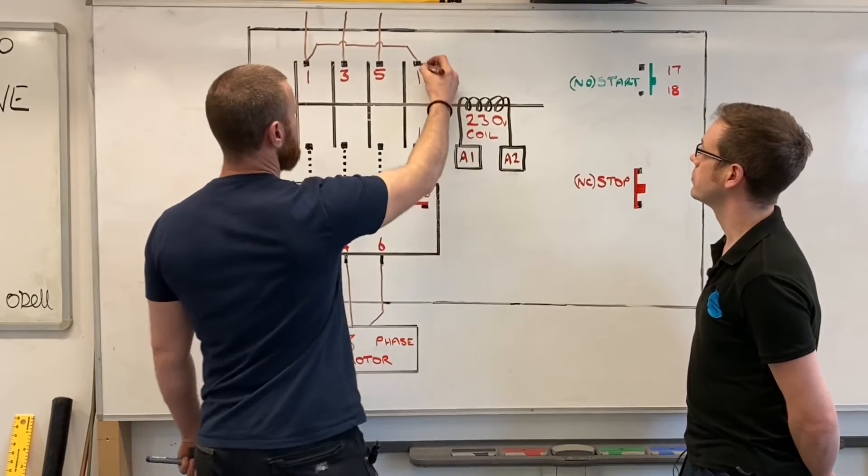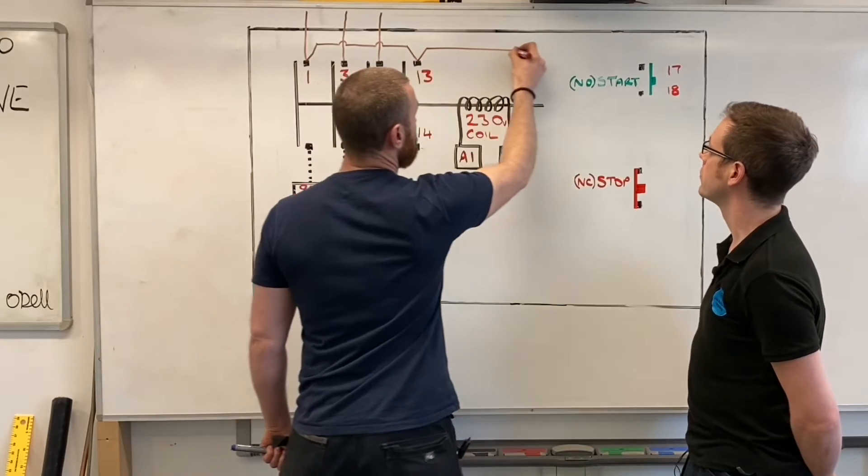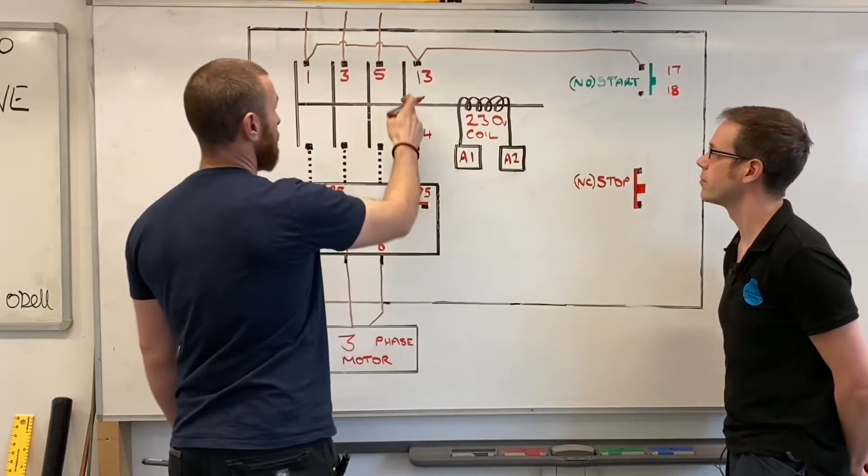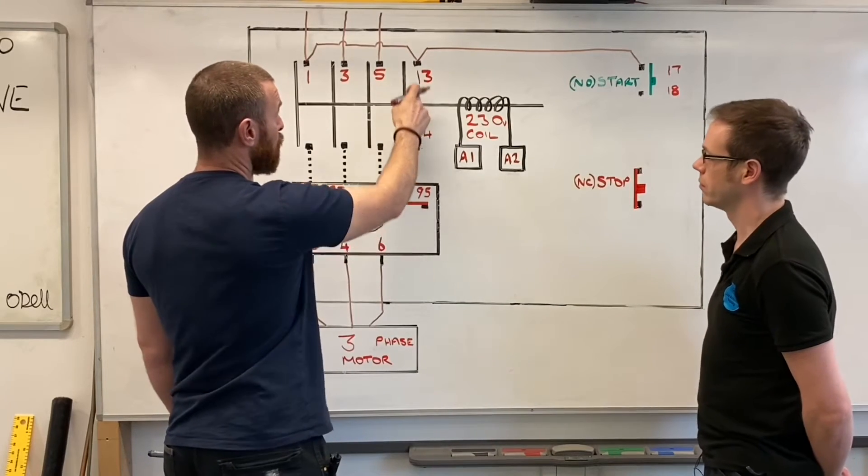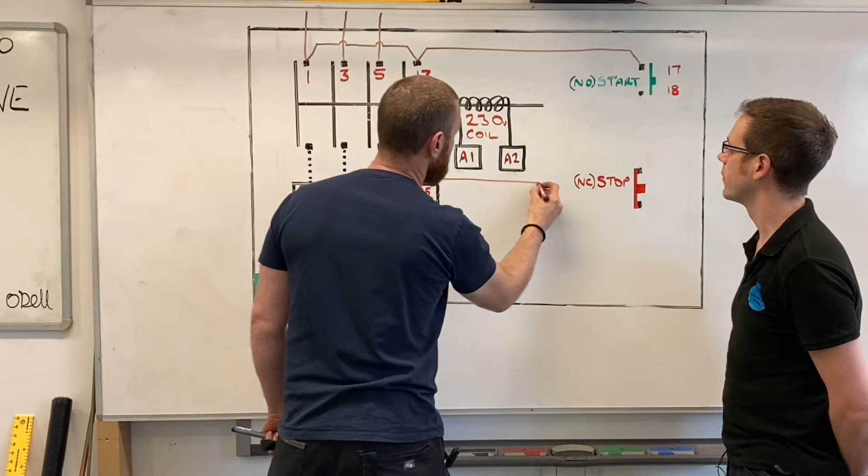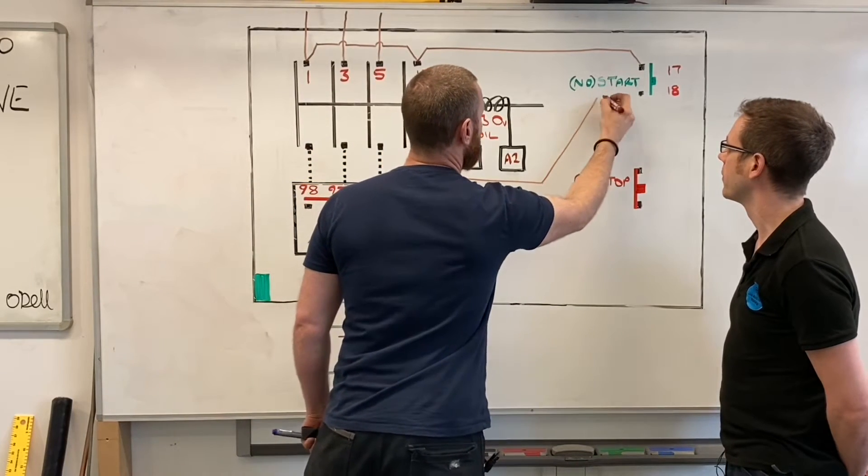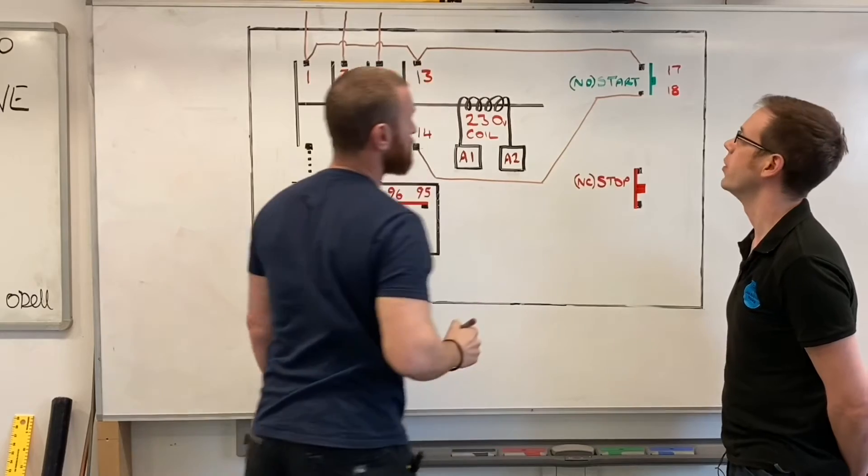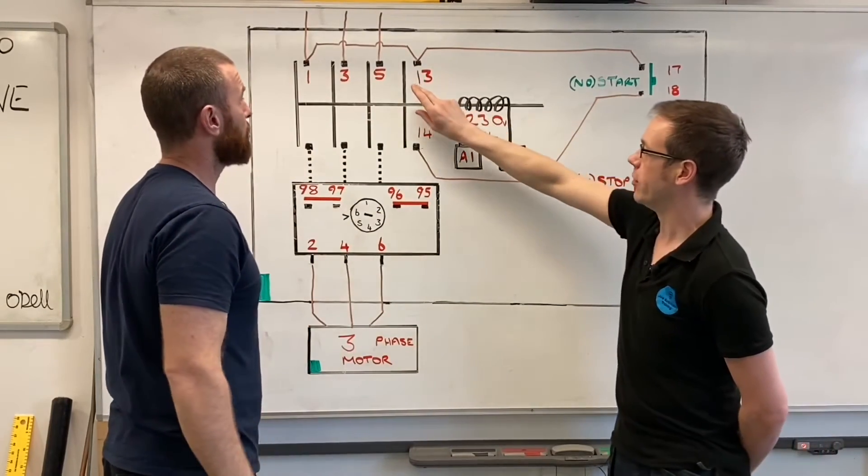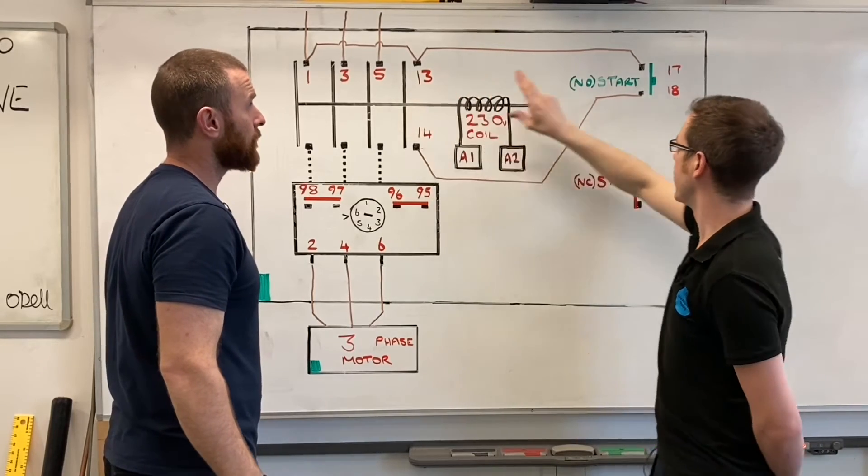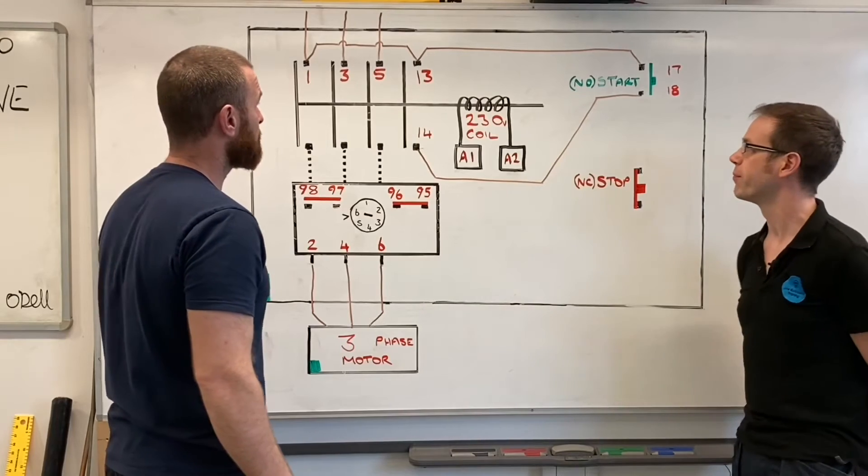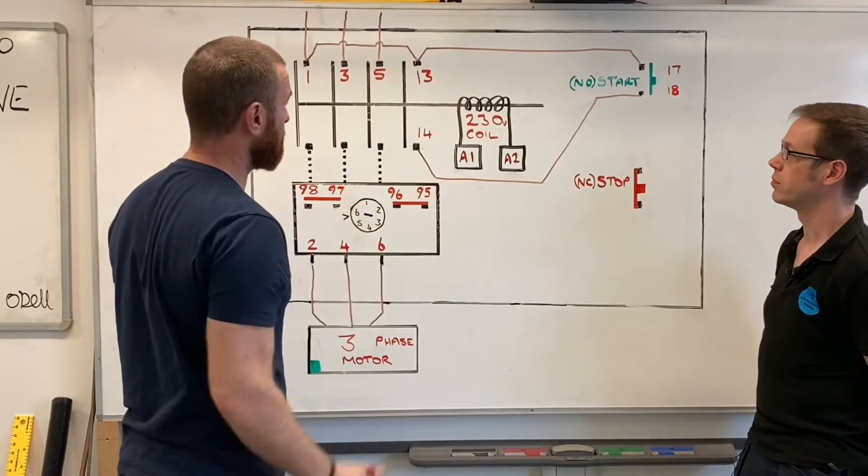We've got our start button over there, so we're going to come across all the way to our start here. Then through the other side of the normally open contacts, we're going to take from number 14 all the way across to number 18. We're seeing what we saw before: the start button and the auxiliary contact, the latching contact, they are in parallel with each other.